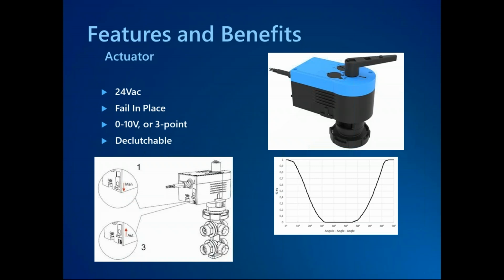Last thing to look for, and it can make your life easier and anybody else that's troubleshooting down the road, is a declutchable actuator. Allows you to manually flip between heating and cooling in the field if we are test and balancing, troubleshooting, or filling and purging the system from an install standpoint. Having someone that can go out there and manually adjust the position of these actuators to make sure water is going to all the right places at the right time, especially if the actuator hasn't been hooked up yet entirely, can be very beneficial.